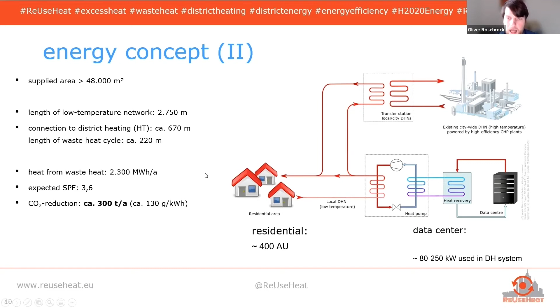How does it work in detail? It's a bit technical right now, I'm sorry for that. As I already said, the base load is covered by the waste heat combined with the heat pump. The peak load is covered by the existing high temperature network, which has up to 130 degrees in summer. The temperatures in the low temperature network are 70 degrees C in the supply flow and 40 in the return flow. There's a small mistake on the slide. This is return flow and this is also return flow. And the temperatures in the cooling cycles of the data center are 25 and 18.